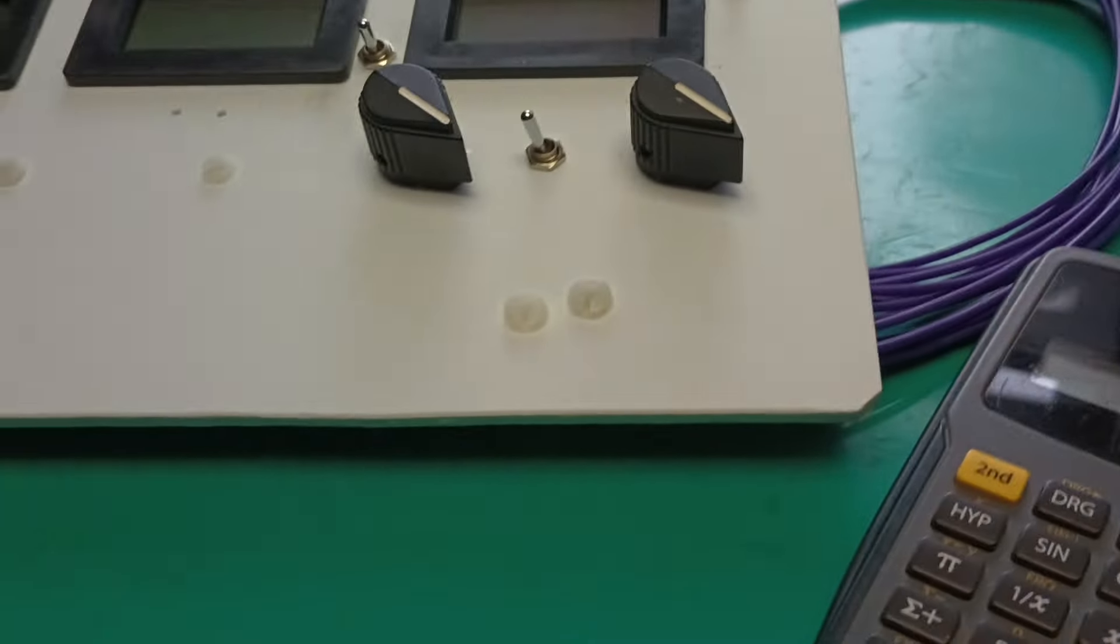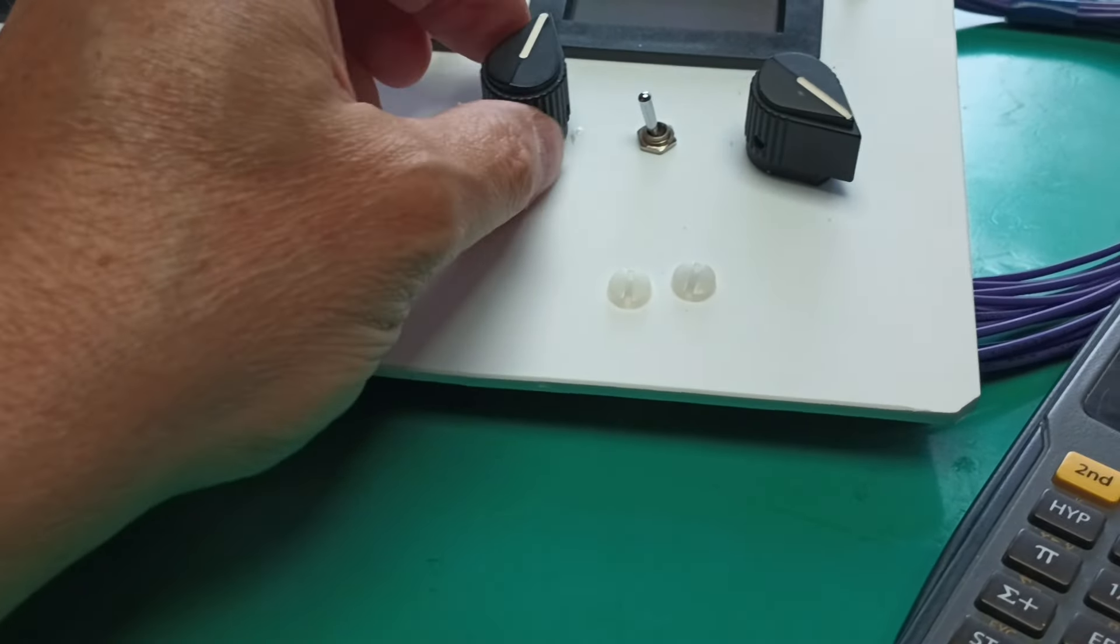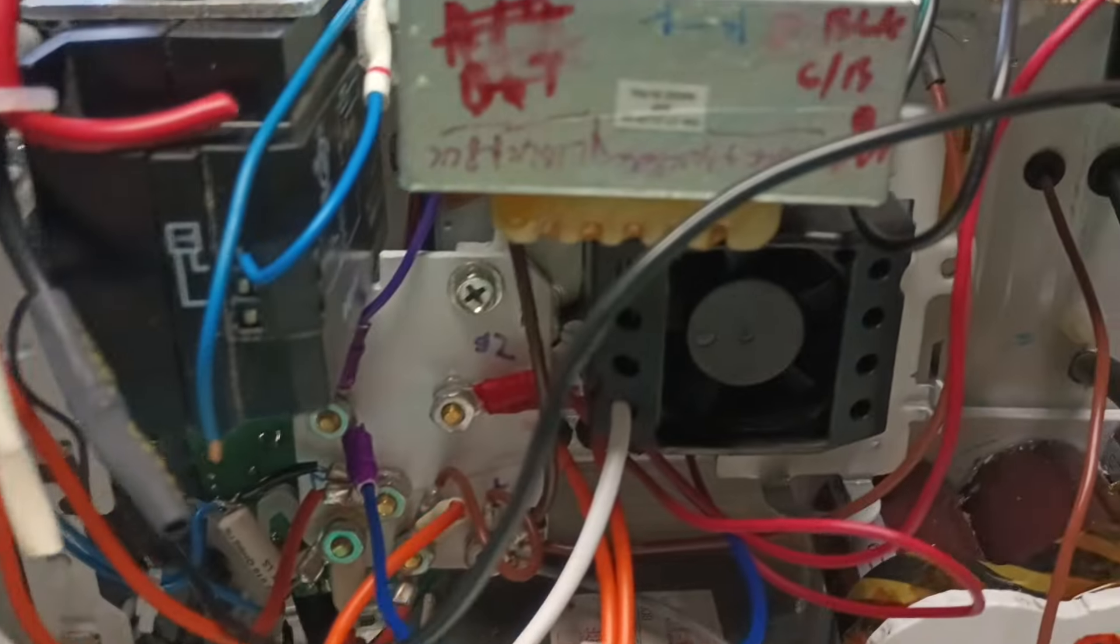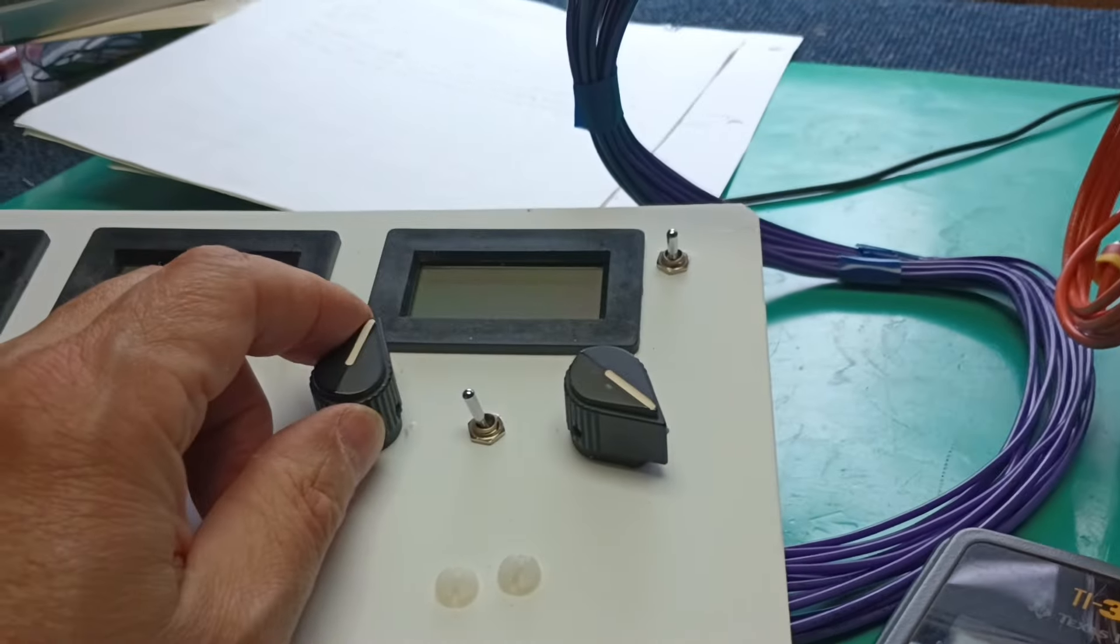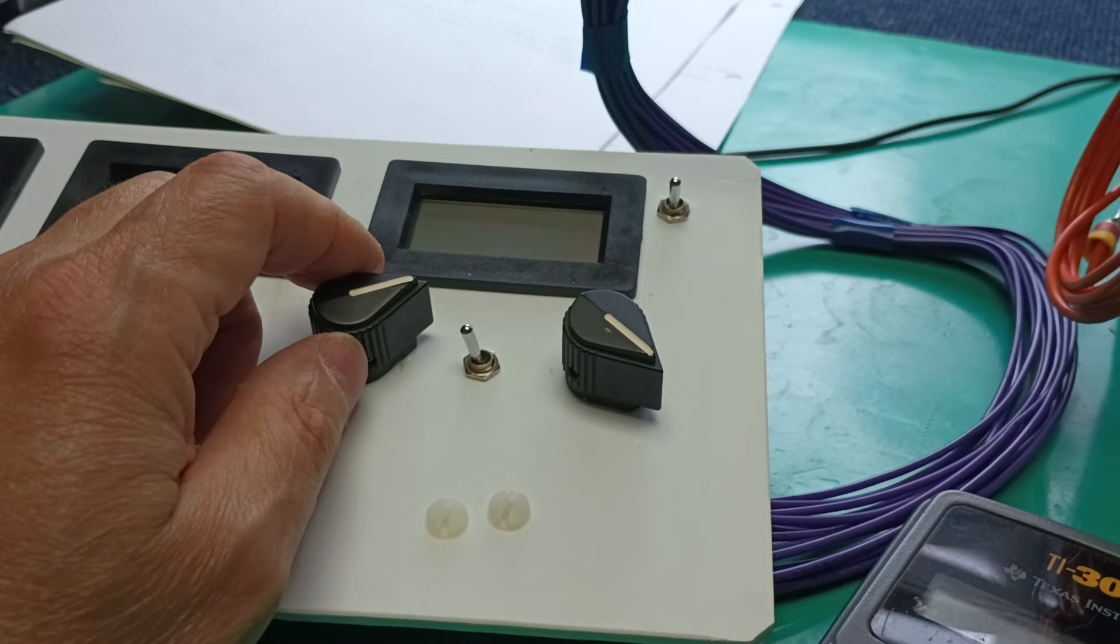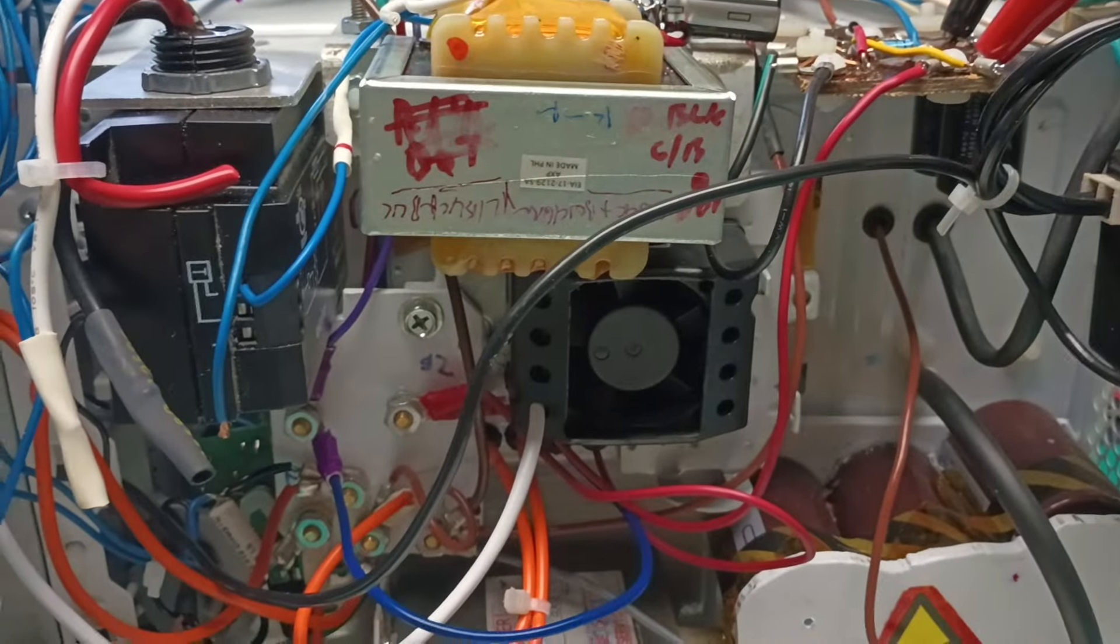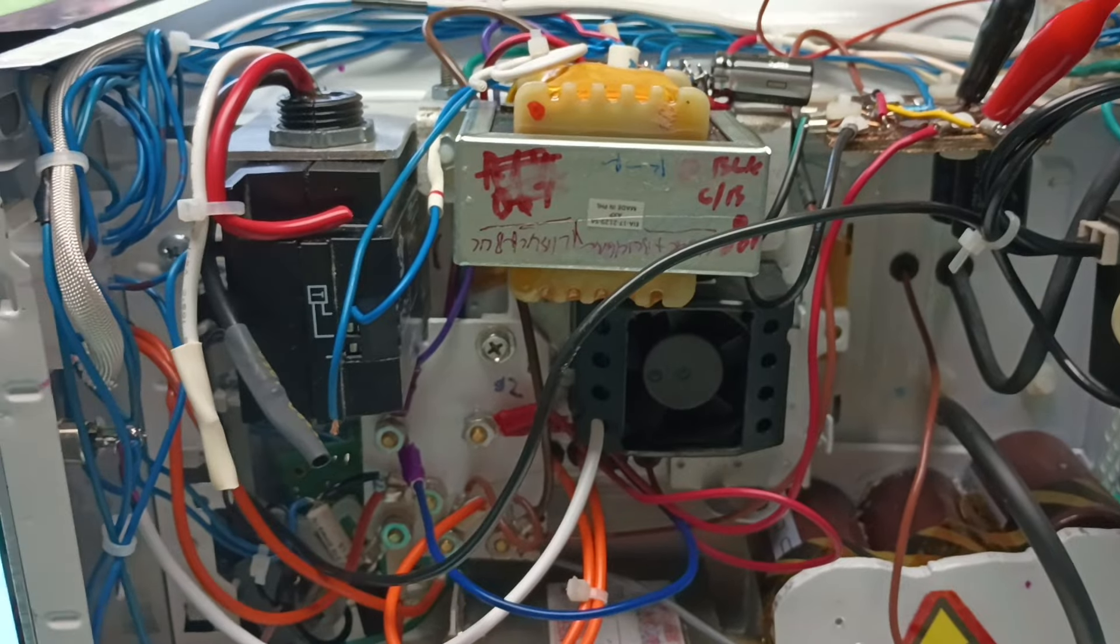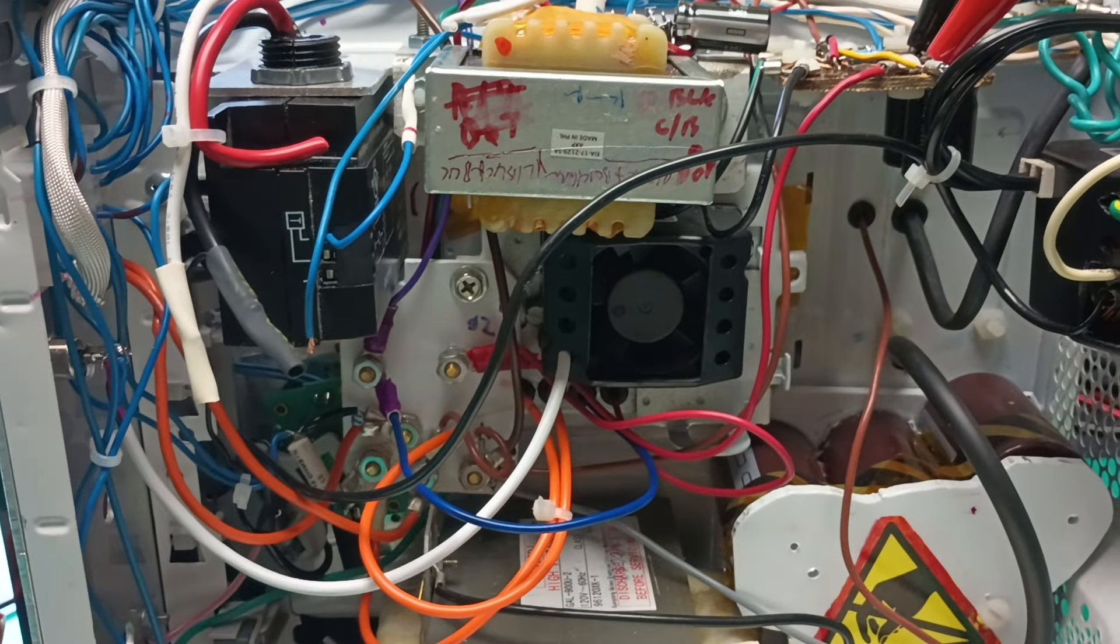What was really strange is when I advanced the voltage control up to about, the voltage would go to 480 or so, and then the power transformer started buzzing and screaming like something's drawing a whole crap load of current. Continue to advance the control and suddenly it would go from 480, jump all the way up to maximum 560, no in between. When it jumped to 560 the buzzing stopped. Now this is extremely strange because it's a whole pile of apparently unrelated symptoms, but they're related.